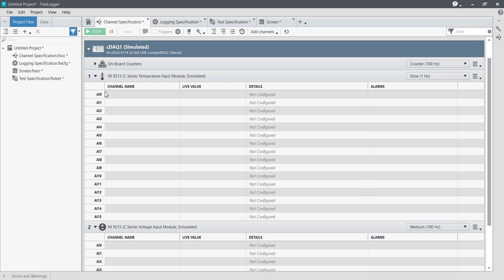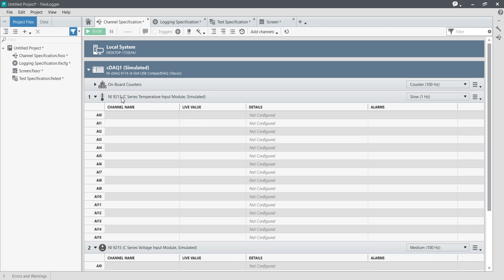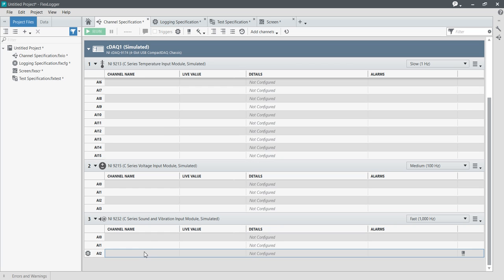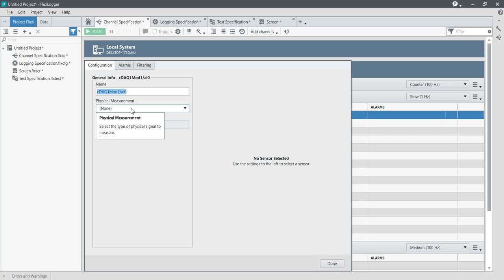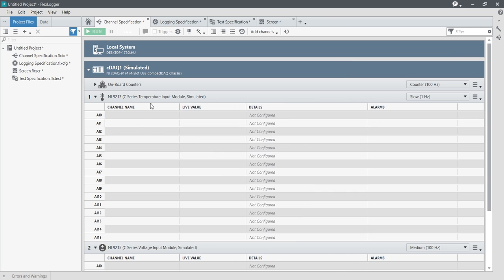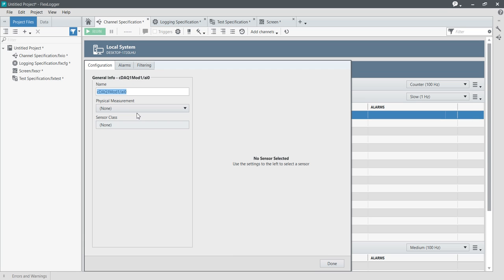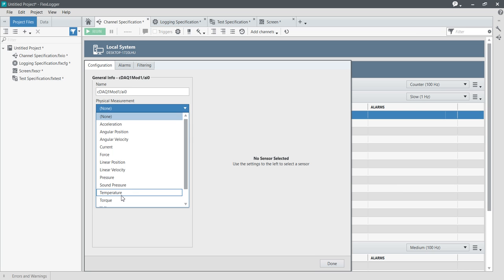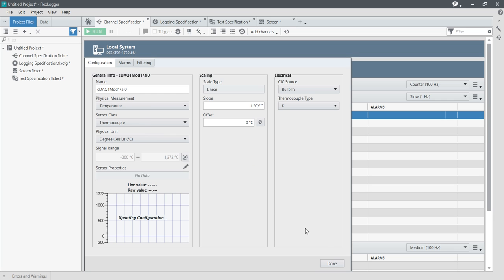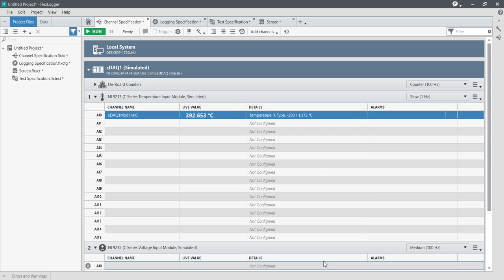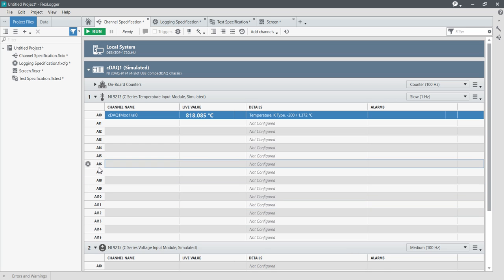Now you can see there is a 9213 temperature module, a 9215 voltage module, and a 9232 vibration module. I am going to double-click to open the temperature module and configure a single channel. The physical measurement type will be temperature and the sensor class will be thermocouple. Press done — it is now configuring and reading the data.